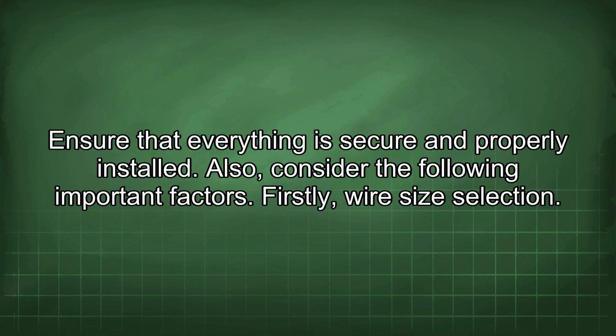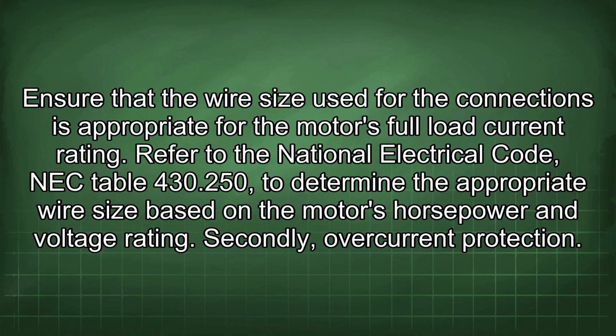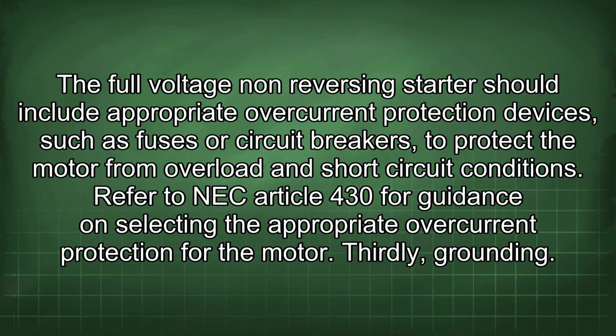Also, consider the following important factors. Firstly, wire size selection. Ensure that the wire size used for the connections is appropriate for the motor's full load current rating. Refer to the National Electrical Code, NEC Table 430.250 to determine the appropriate wire size based on the motor's horsepower and voltage rating. Secondly, overcurrent protection. The full voltage non-reversing starter should include appropriate overcurrent protection devices, such as fuses or circuit breakers, to protect the motor from overload and short circuit conditions. Refer to NEC Article 430 for guidance on selecting the appropriate overcurrent protection for the motor.